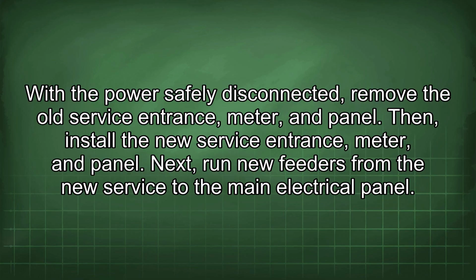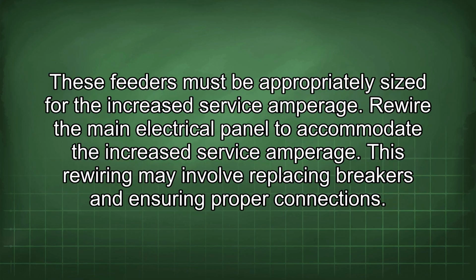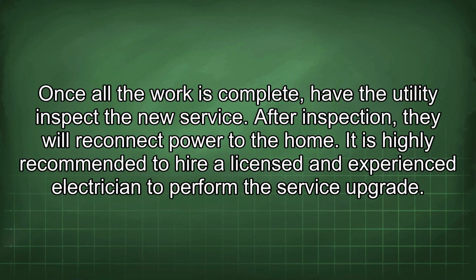Next, run new feeders from the new service to the main electrical panel. These feeders must be appropriately sized for the increased service amperage. Rewire the main electrical panel to accommodate the increased service amperage. This rewiring may involve replacing breakers and ensuring proper connections. Once all the work is complete, have the utility inspect the new service. After inspection, they will reconnect power to the home.